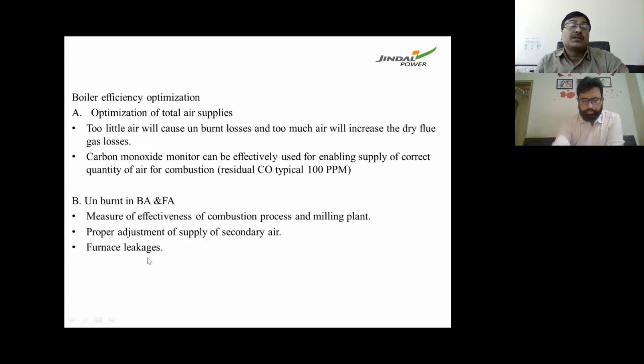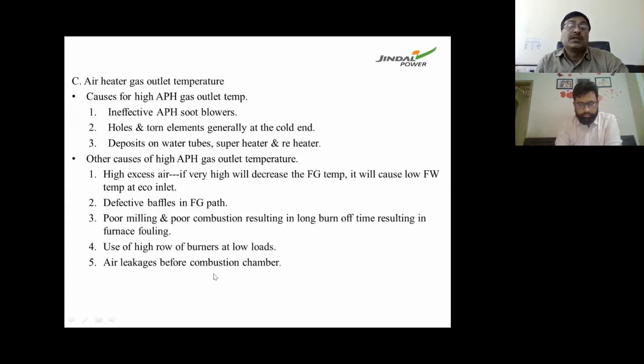Third one is APH gas outlet temperature. What are the causes of high APH gas outlet temperature? This is because of ineffective APH soot blowing, holes and torn elements at the cold end, deposits on water tubes, superheater tubes, and reheater tubes. Other causes are high excess air, defective baffles in the flue gas path, poor milling and poor combustion. This results in long burn-off time, resulting in furnace fouling, use of a high row of burners at low loads, and air leakages before the combustion chamber.